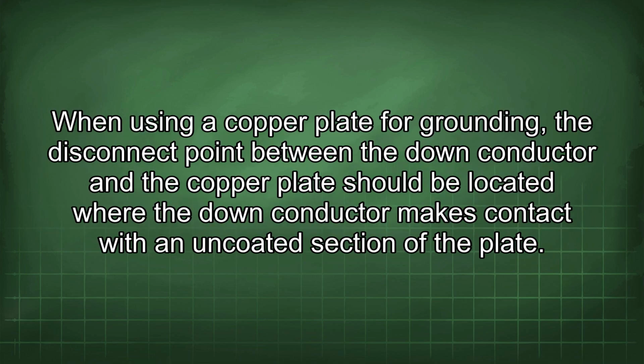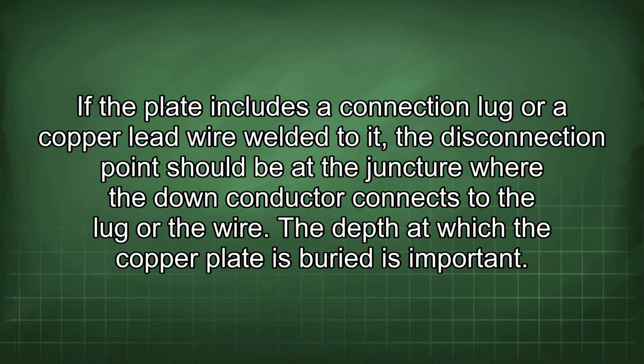When using a copper plate for grounding, the disconnect point between the down conductor and the copper plate should be located where the down conductor makes contact with an uncoated section of the plate. If the plate includes a connection lug or a copper lead wire welded to it, the disconnection point should be at the juncture where the down conductor connects to the lug or the wire.